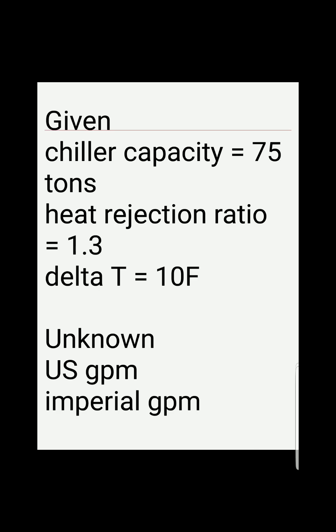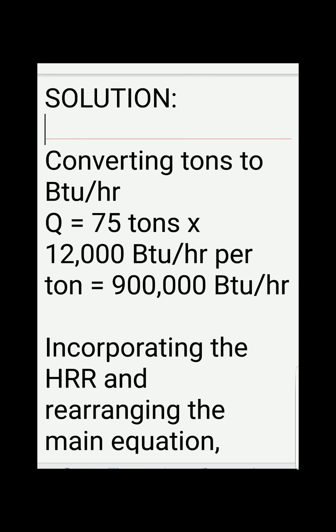For the solution, first we need to convert our given tonnage to BTUs per hour. To do that, we multiply 75 tons times 12,000 BTU per hour per ton, giving us a capacity of 900,000 BTU per hour. The next step is to incorporate the heat rejection ratio into the main equation.